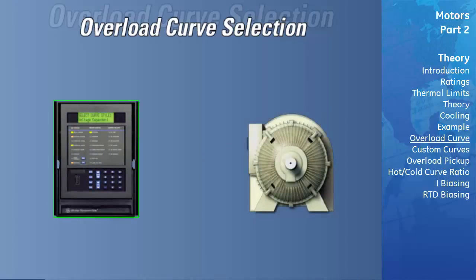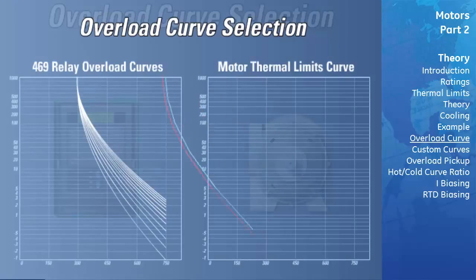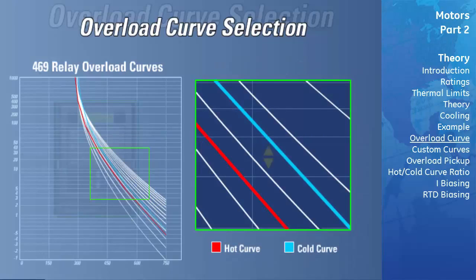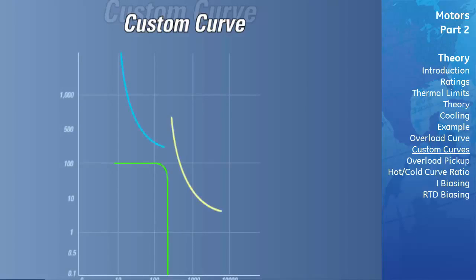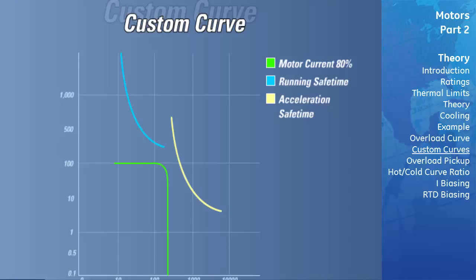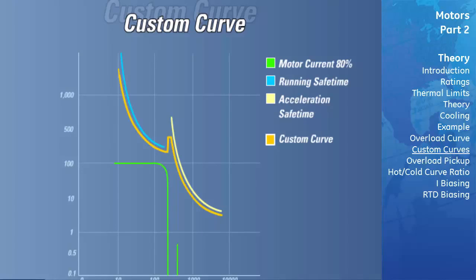Overload Curve Selection. The modern digital relay has multiple standard overload curves which can be chosen to provide accurate protection for the motor. In selecting a curve, the engineer would overlay the standard curves to determine the best fit. The overload curve should be chosen such that it is just below the cold thermal limit and above the hot thermal limit. With the hot-cold curve ratio programmed correctly, the overload curves are automatically adjusted whether the motor is hot or cold. A custom overload curve feature allows users to tailor the relay's thermal damage curve to the motor, allowing a successful start without compromising protection, by entering trip times for 30 predetermined current levels.